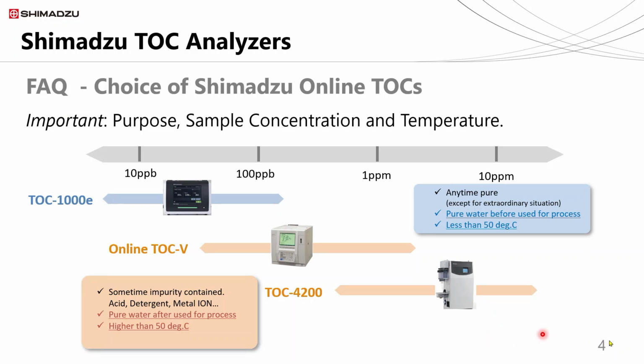With regards to online TOC analyzers today, it's very important that you choose the correct online instrument for your application. And to choose the proper model, you have to know about the purpose, sample concentration, and temperature at least. After that, the correct instrument can be advised to you by your local Shimadzu representative. For example, if you need to monitor and check your online pure water line in your laboratory, TOC-1000e is the best selection for you.